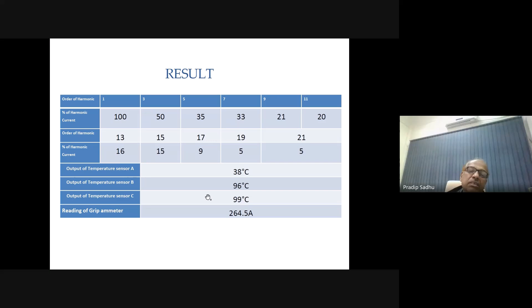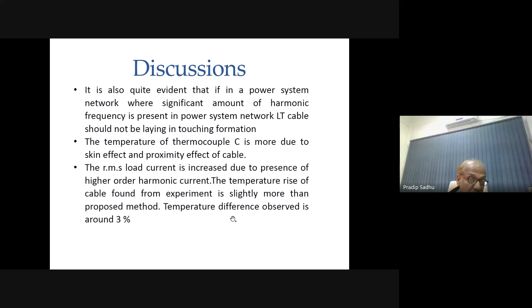It is also quite evident that if in a power system network there is a significant amount of harmonic frequency present, the power system network LT cable should not be laid in touching formation. The temperature of thermocouple C is more due to the skin effect and proximity effect of the cable. The temperature difference observed is around 3%. And due to this temperature rise, the life of the cable will be shortened due to these harmonics. So these are the discussions.